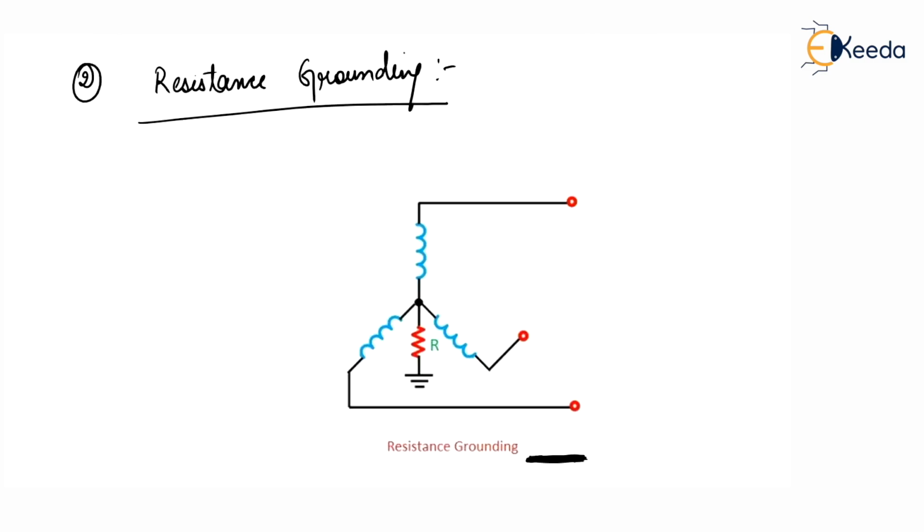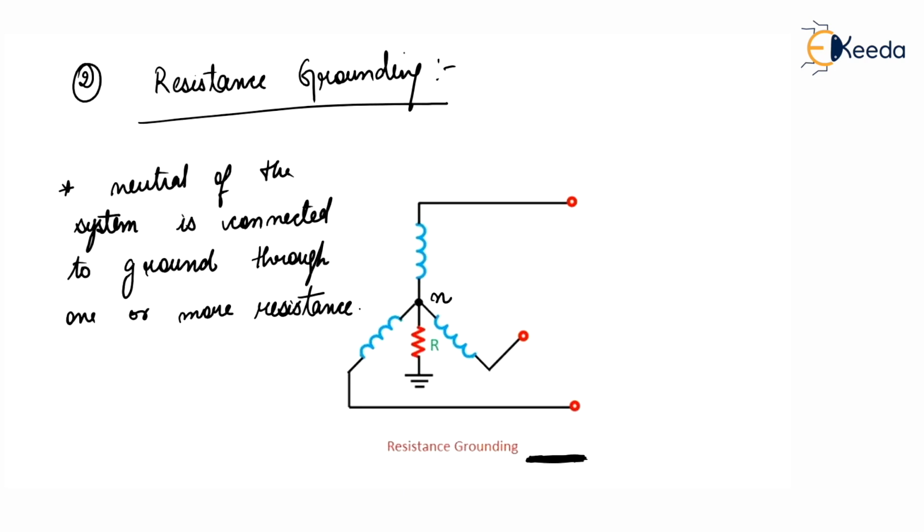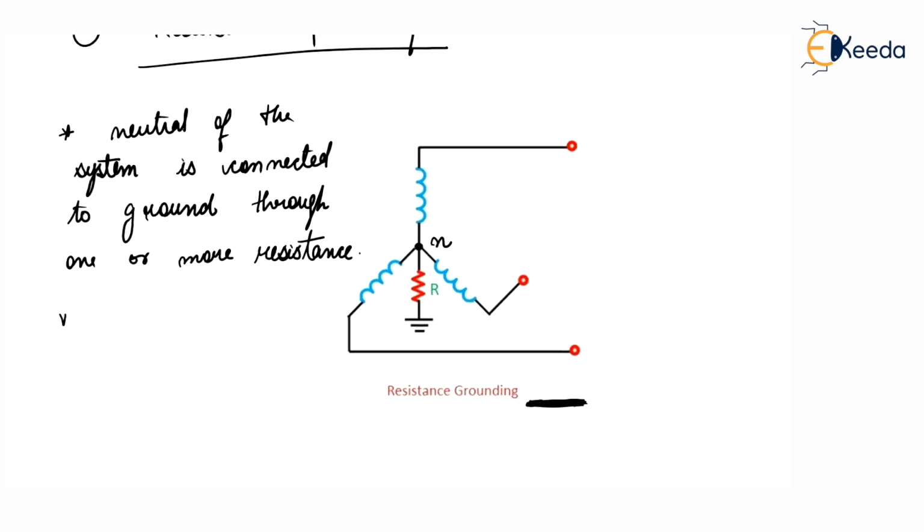Now, in this type of neutral grounding, resistance grounding, the neutral of the system, as shown in this diagram, is connected to ground through one or more resistances. So, resistance grounding limits the fault current.